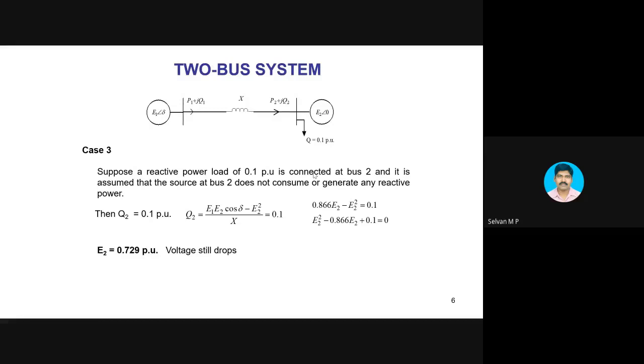So machine 1 has certain capability to supply reactive power. Beyond that, it cannot supply. Then what will happen if you keep on increasing reactive power load at the receiving end? The voltage will keep on reducing. At one point of time, the voltage will come below 0.5, 0.4. Then suddenly the voltage will come down to zero. That phenomenon is called voltage collapse in power system.